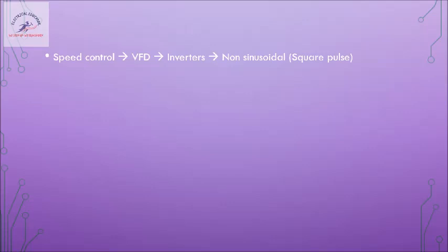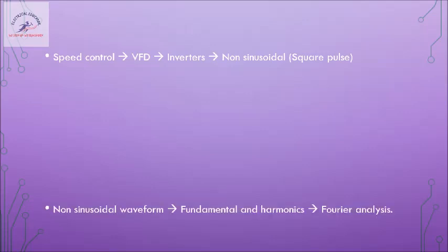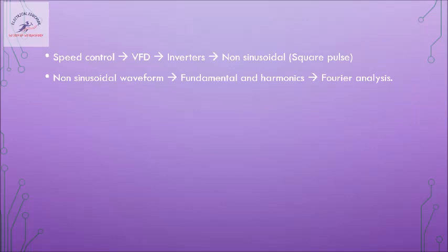We go for V/f control, and varying the frequency of a sinusoidal supply is possible only by rectifying it and then feeding it through an inverter. These inverters give us pulsed square waves — this is one of the techniques where we get square pulse waves, called pulse width modulation. The output of the inverter is a square wave which is not sinusoidal, so we are going to study the effect of feeding these square pulses or non-sinusoidal waveforms to the stator of the induction motor and how it affects performance.